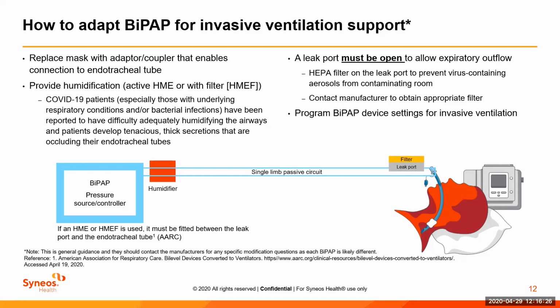However, single limb circuits never went away. They always stayed from the 80s on. We see them typically in LTACs, at home use, and in the late 80s, they got very positive feedback on using these single limb circuits for non-invasive ventilation. If we stop calling these machines BiPAP and look at them as non-invasive ventilators, whether they be single limb or double limb, it's easy to transition to thought of how this works. So let's go from the BiPAP machine on the left and slide up the single limb circuit after it's passed over that active heater pot, that active humidifier, and it connects to the patient.